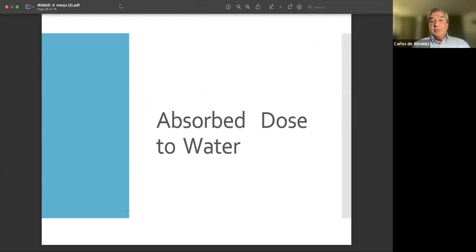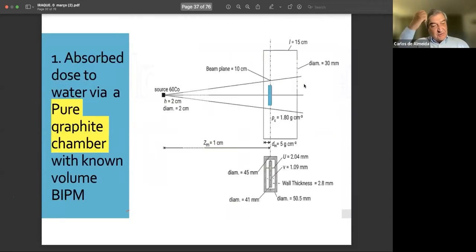Now, when we talk about absorbed dose to water, that's a completely different ball game, let's say. The next slide shows that the first option is to use a graphite chamber, a pure graphite chamber with 99.99 graphite inside of a graphite phantom. This chamber should have its dimensions very well measured, so you know accurately the volume. And then it is exposed to a field size of 10 by 10, like we said, under the reference conditions.